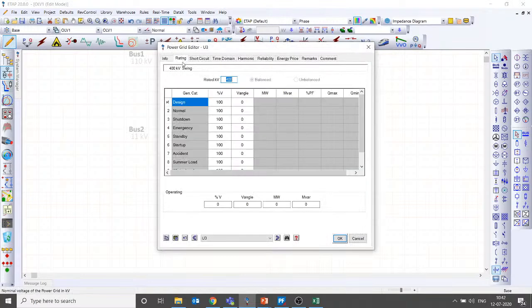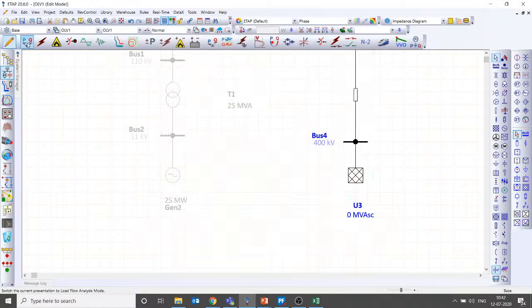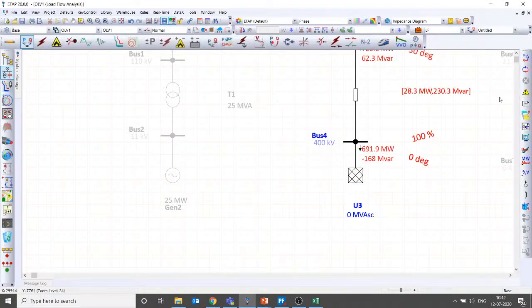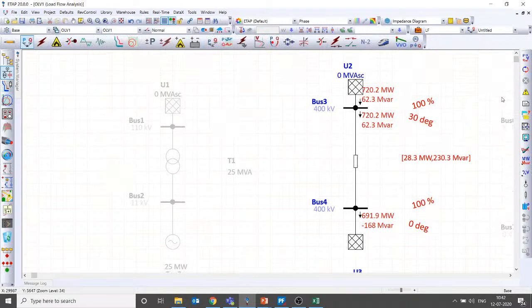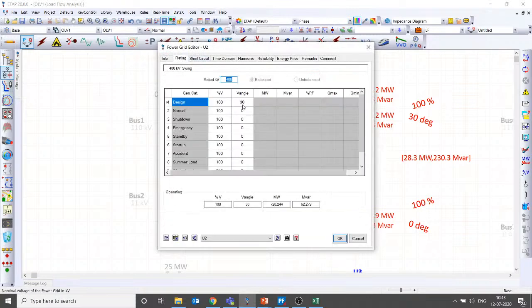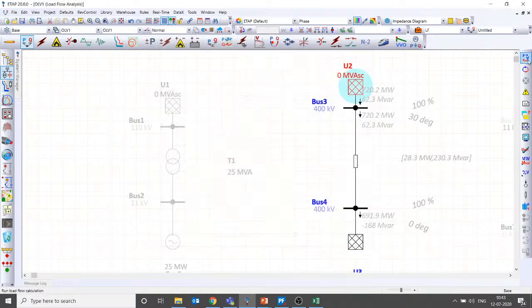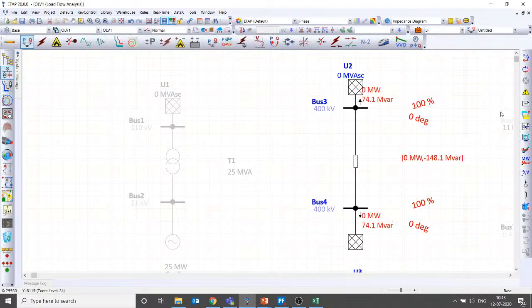Here also I have assumed it's right. Because of the angle difference, the power is flowing, which you can understand. Here I have given 30 degree, here I have given 0 degree, so the power flow is about 720 megawatt. If I make angle 0, then there will not be any power flow. So if you are modeling multiple slack bus, then you need to understand why it is multiple slack bus. That is to answer Sasikumar.